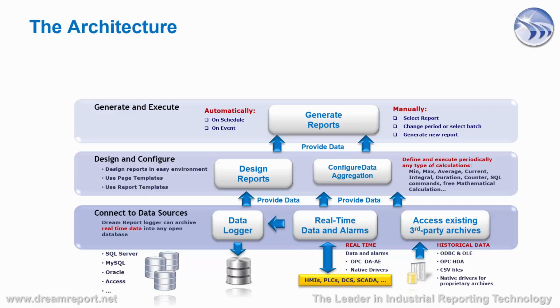After configuring a report, you can set up how the report will be generated. As mentioned previously, a report can be triggered on any schedule, whether it's calendar-based, periodic, or specific times of the day. It could be event-driven, based on any real-time value in an HMI or a PLC. And finally, reports can be manually generated through a runtime management console, through an ActiveX control, through a command line, or even being called from a remote application.